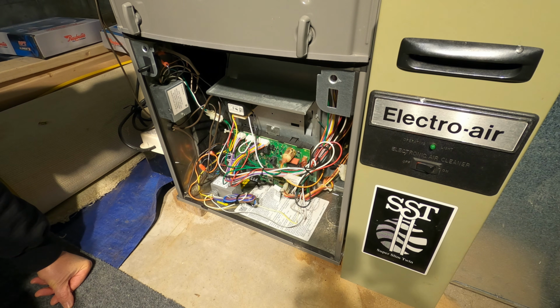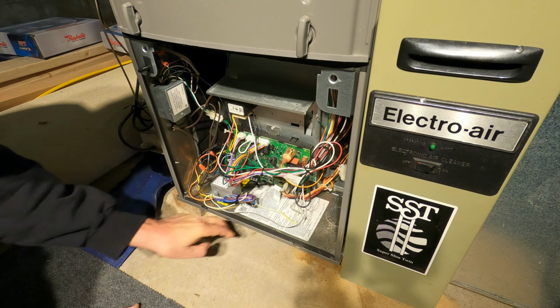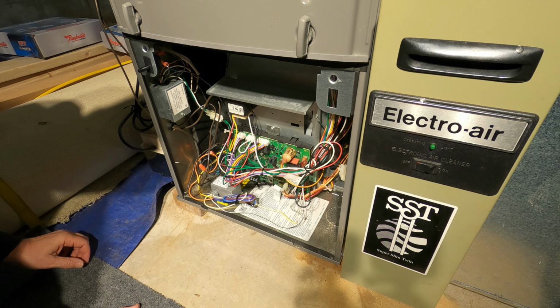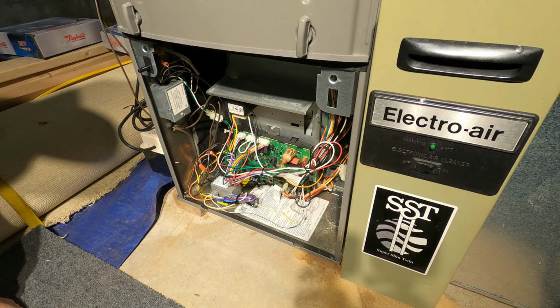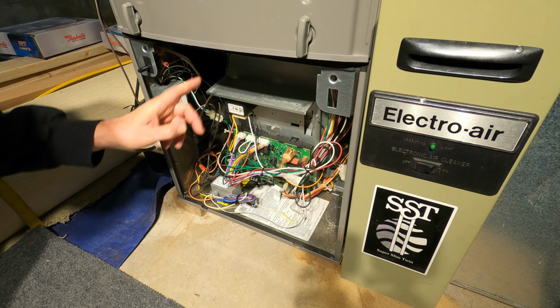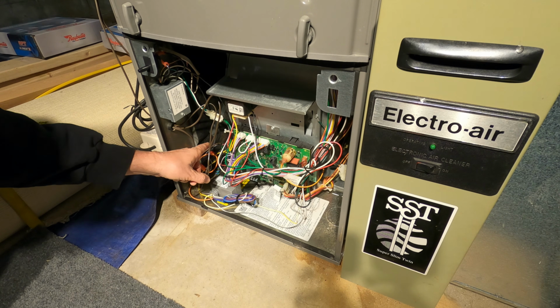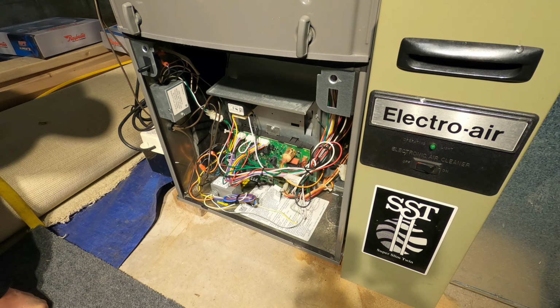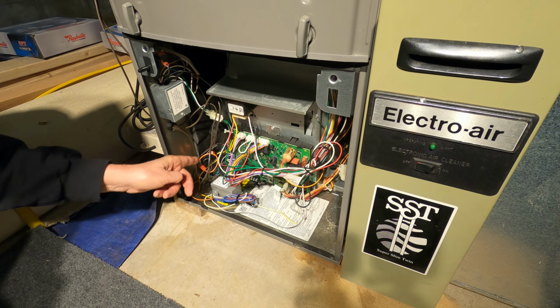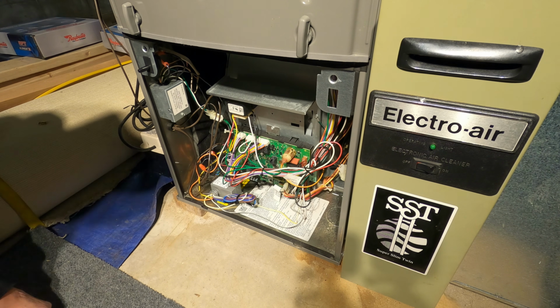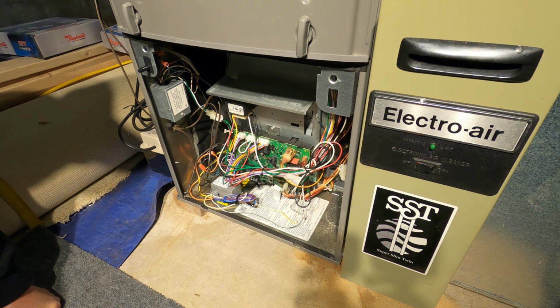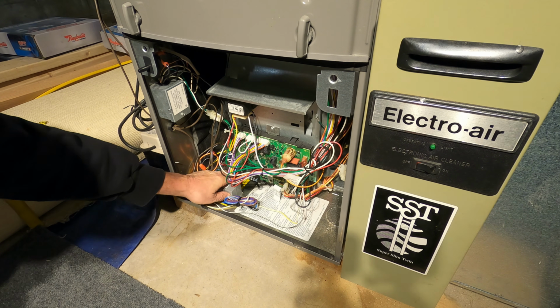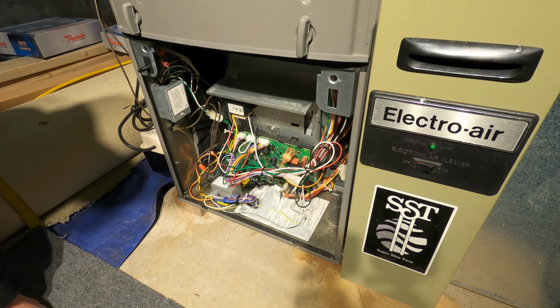And that's because if the evaporator ices up, water can drip down in and pool up inside here. So as it happened, that drain tubing on the evaporator plugged, and I had water dripping down inside here, and it was starting to pool up back there, but there's actually enough openings in the bottom there. There's like spaces between the sheet metal. It's actually not very impressive that there's big leaks in the bottom, but the water dripped out, and so it never accumulated enough to touch the relay.